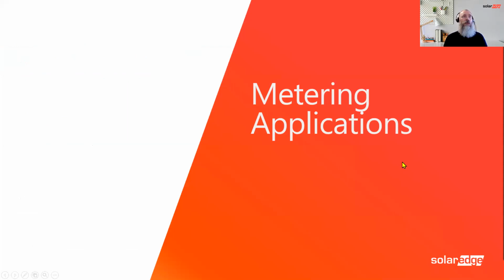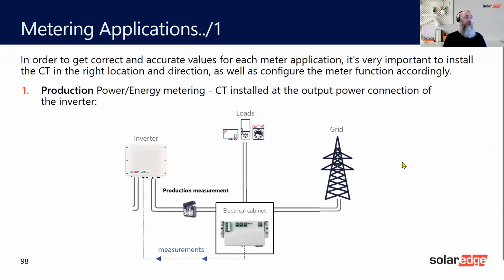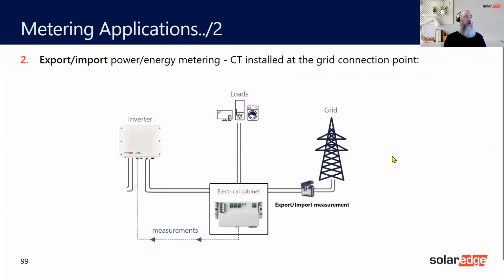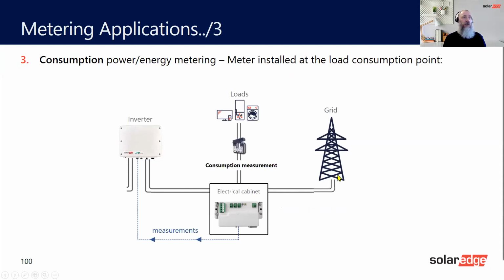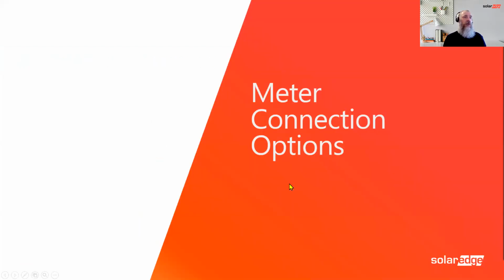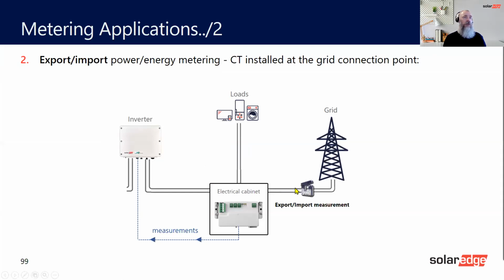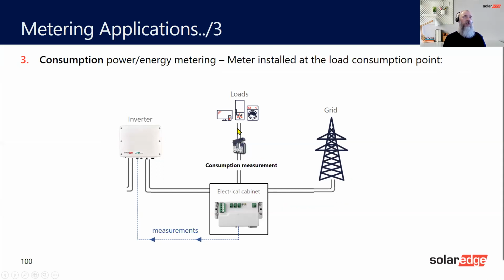So what would you use it for? Let's have a look. You want to get the correct information, so what the inverter is doing, so you can measure production. The CT would be installed by the inverter, and that would measure the production. Application 2 is export and import. Again, the meter's in the same place, but the CT is now at the grid area, and the grid arrow is pointing to the grid. For consumption, it's pointing to the load. Okay, so we go back one. So for export and import, it's pointing towards the grid, and for consumption, it's pointing towards the load.